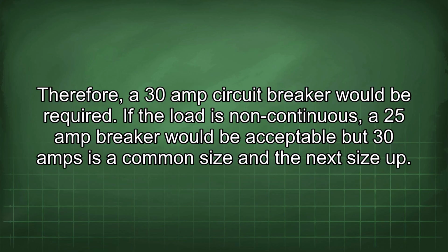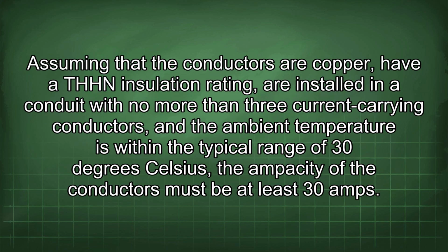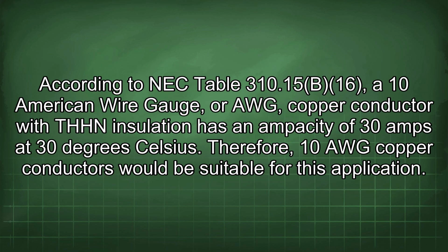Assuming that the conductors are copper, have a THHN insulation rating, are installed in a conduit with no more than 3 current-carrying conductors, and the ambient temperature is within the typical range of 30 degrees Celsius, the ampacity of the conductors must be at least 30 amps. According to NEC Table 310.15(B)(16), a 10 American wire gauge, or AWG, copper conductor with THHN insulation has an ampacity of 30 amps at 30 degrees Celsius. Therefore, 10 AWG copper conductors would be suitable for this application.